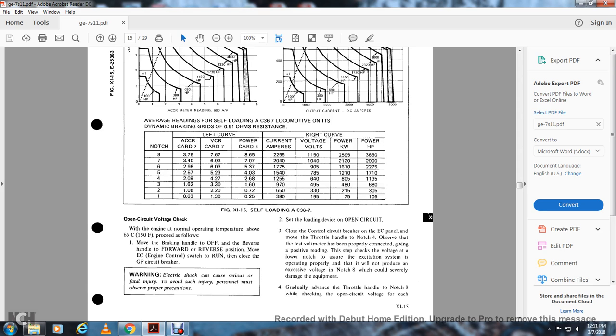With the self-loading device open circuit, close the control circuit breaker on the engine control panel. Move the throttle handle to notch 4. Observe the testing voltmeter that has been properly connected. It should give a positive reading. Check with the voltage at the lower notch to ensure the excitation system is operating properly. Excessive voltage in notch 8 could severely damage the equipment.